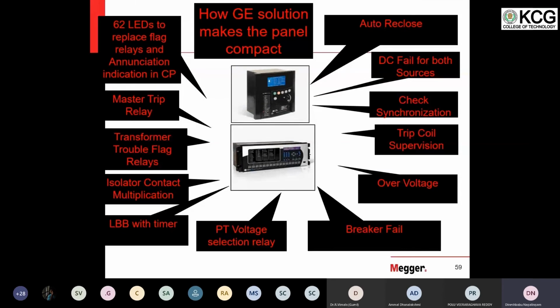Whereas a numerical relay, you have 2 laptops. One laptop fails, immediately you go for the other laptop. That means you have 100% redundancy. So that is what is implemented in numerical relay technology. What we do here is, instead of using 15 relays, electromechanical relays, we will use 2 or 3 numerical relays. One will stand as a backup, but each relay is 100% having all the protection functions. So if one relay fails, still 100% all the protection function is available in the system. This is the first point that we need to understand. Now let us see the second point.